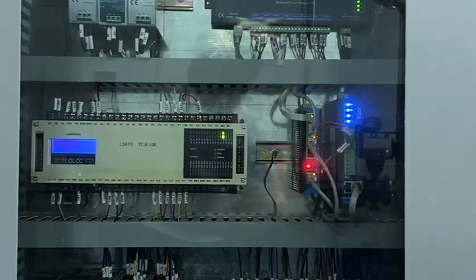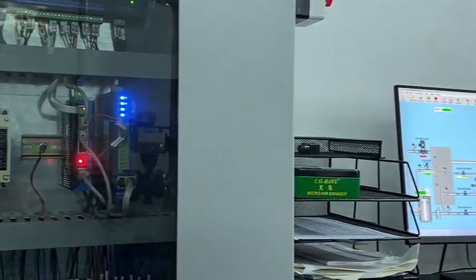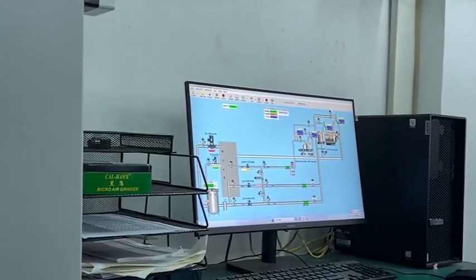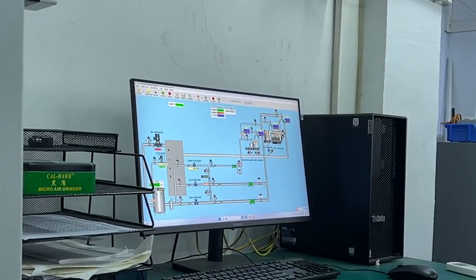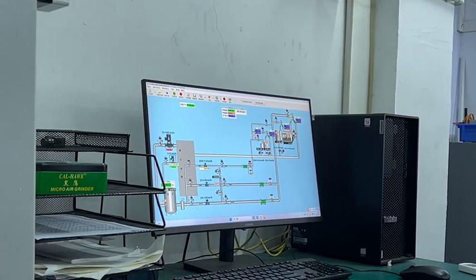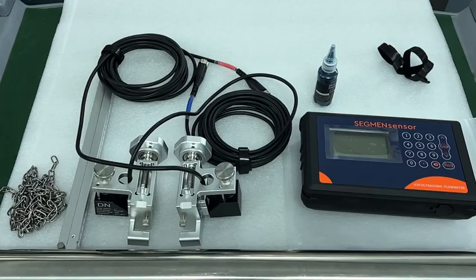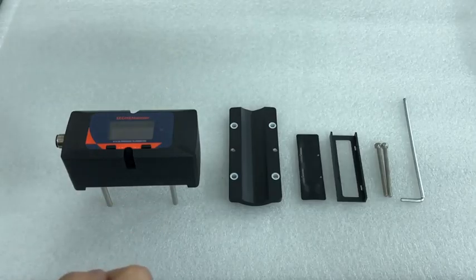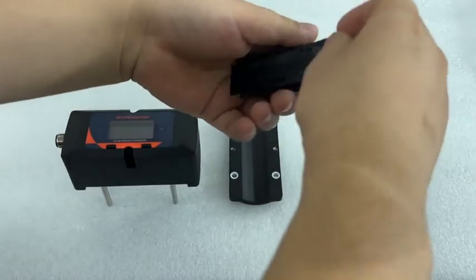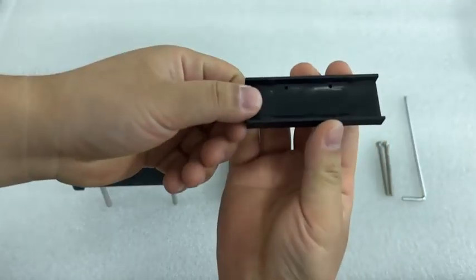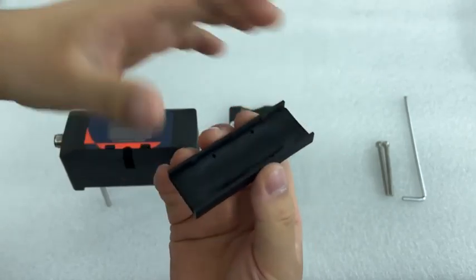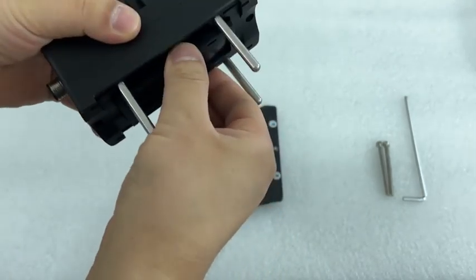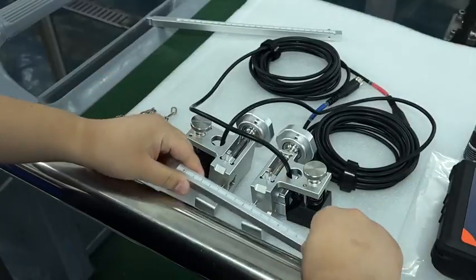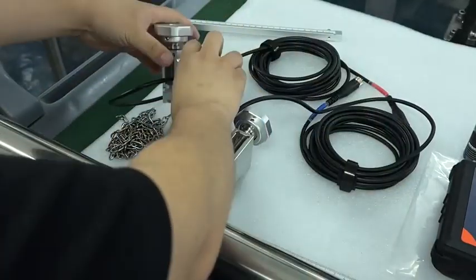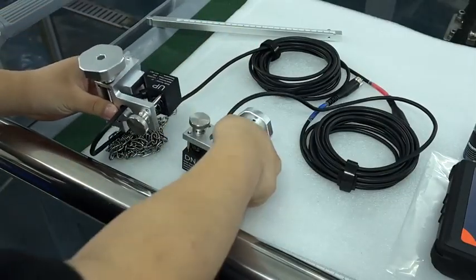Our engineers use this system to set the target flow rate and monitor the comparison between the unit under test and the reference standard. Before testing begins, every meter is unpacked and inspected. This is a complete SEGMEnsensor clamp-on ultrasonic flow meter kit. The package contains the main transmitter unit, 2 transducer probes, stainless steel mounting brackets, chain fasteners, signal cables, and a tube of acoustic coupling gel. Every component is accounted for before installation begins.